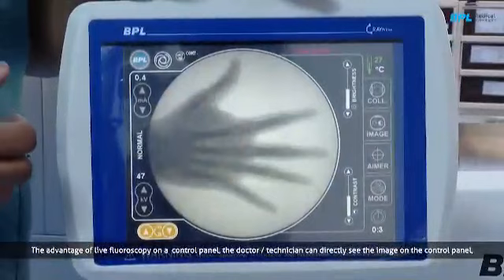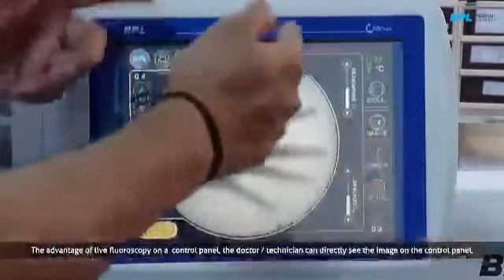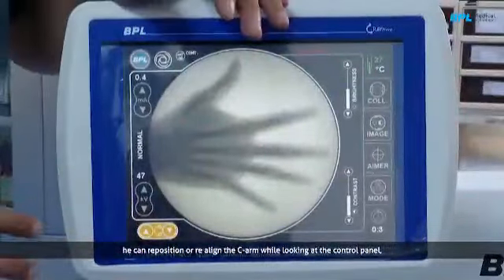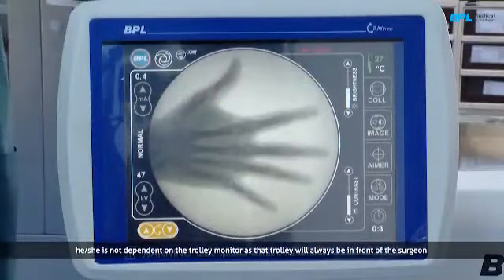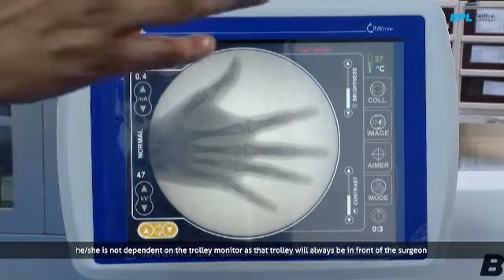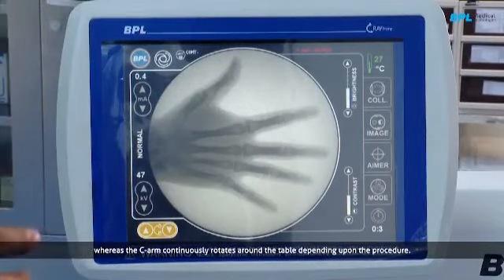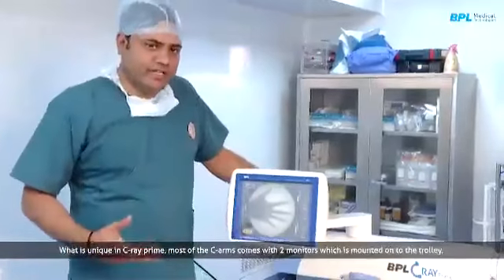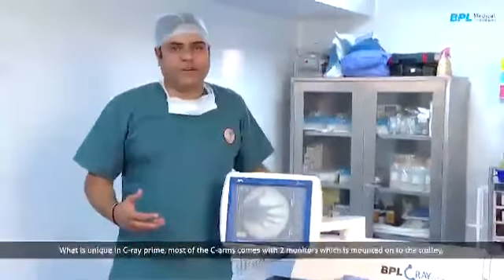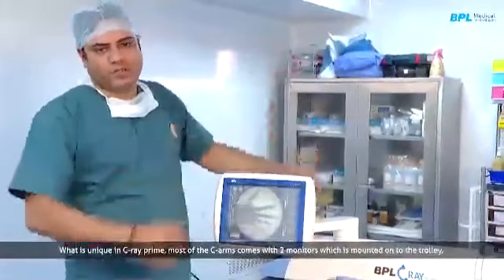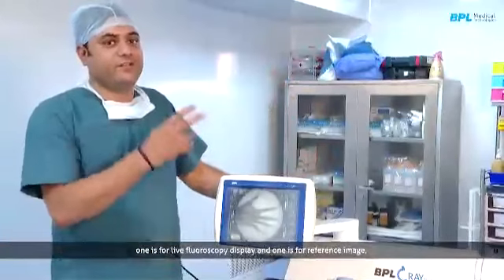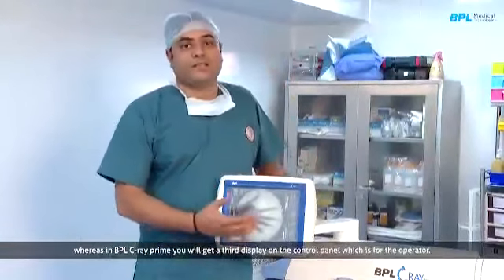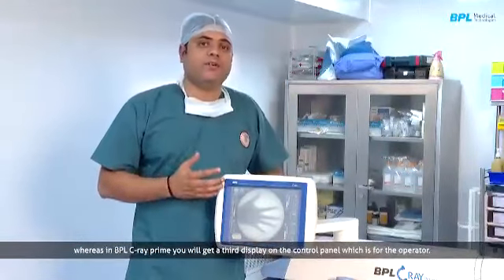And what is the advantage of live fluoroscopy on a control panel? The technician can easily see the image on this panel, and he can reposition or realign the C-arm while seeing this control panel. He is not dependent on the monitor at the trolley, because that trolley is always in front of the surgeon, whereas the C-arm keeps rotating around the table depending on the procedure. What is unique in C-Ray Prime? Most C-arms come with two monitors mounted on the trolley. One is for live fluoroscopy display and the other is for the reference image. But here in C-Ray Prime you get a third display on the control panel, and this is for the operator.